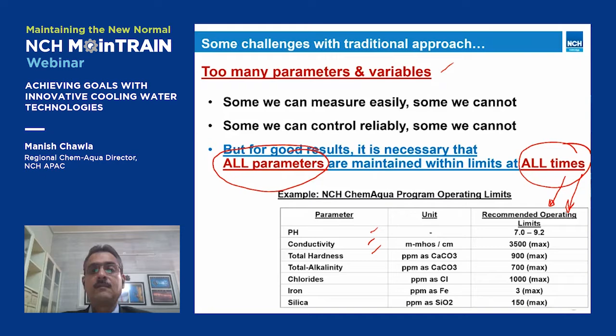Then there's the evaporation in the cooling towers, a highly dynamic system where the evaporation rate changes all the time. The evaporation rate decides how much blowdown and makeup water we need, in addition to the makeup water quality. But the evaporation rate itself keeps changing so frequently, it's different in summer, different in winter, different in the morning, and different at night.